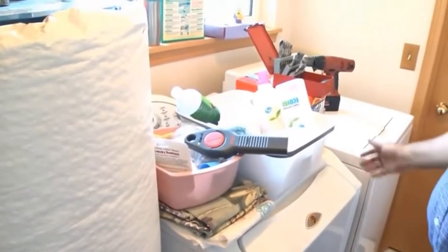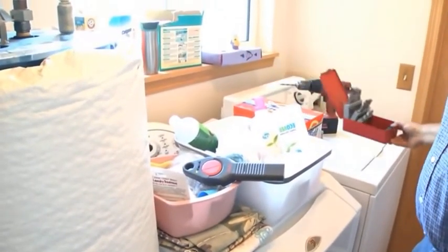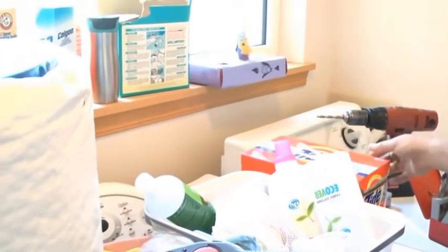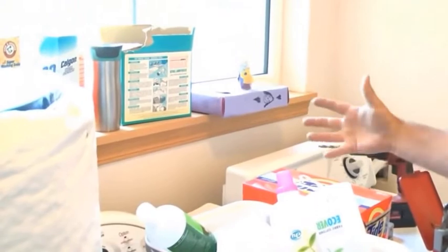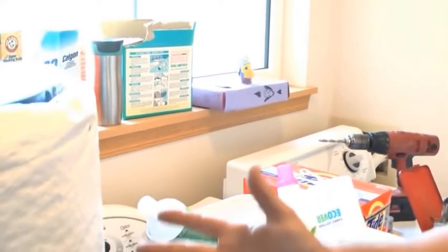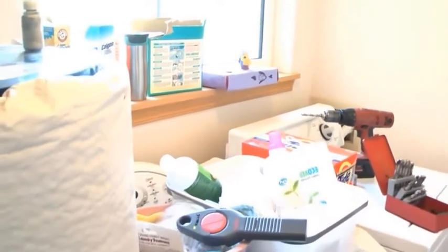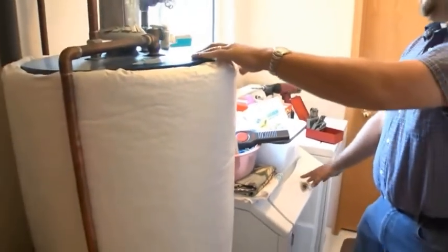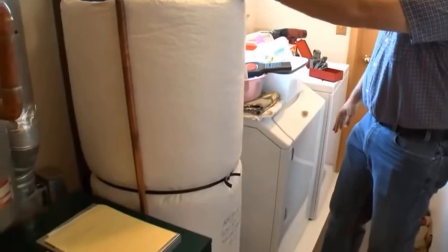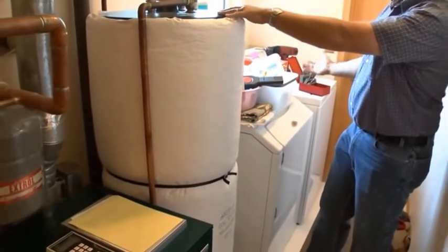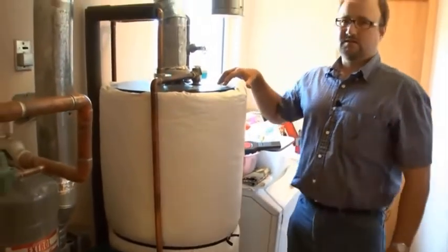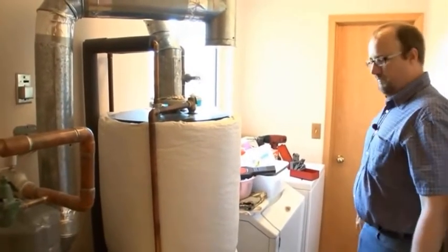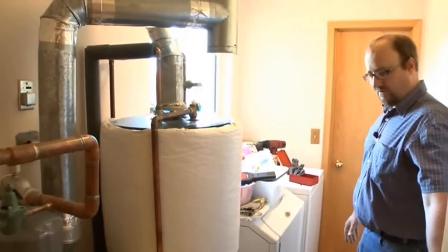One of the things you want to avoid is rooms that have soaps. The fumes from the soaps and the bleaches actually go through the appliances, and most manufacturers do not recommend having your fuel appliances in the same room as these chemicals, because it will deteriorate the heat exchanger on these. The other thing about this room is it's a fairly small room. The door's probably shut quite often.